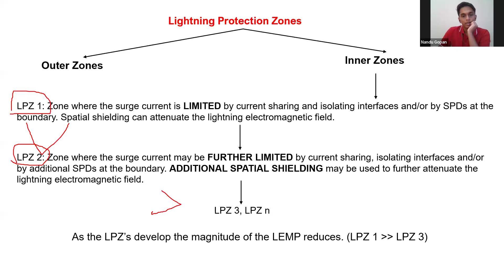So here I have put LPZ1 is more than LPZ3. That means the surge currents or induced magnetic field H or I will be very less compared to lightning protection zone 1. That is what it means. So you have to continue until your equipment can withstand the impulse current. But for general cases, most of the equipment can be placed in zone 1 of the standard. It is not a problem, but we are talking about sensitive equipment and sensitive electronics. So for that, if you want good lightning protection, you will need to do all these things. You have to categorize it by zone 0, zone 1, zone 2, zone 3, and you have to categorize the equipment.